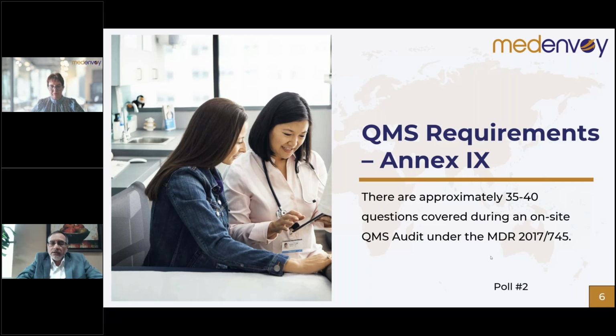When we are on site auditing your quality management system, we are assessing the processes that you have put in place to demonstrate compliance against the regulation. And then the output of those processes will be your actual technical documentation, reviewed by a technical expert. In most notified body audits, you have to get through this segment first. Once you have shown that you have adequate procedural and process controls in place, only then will your technical documentation be eligible for further review.